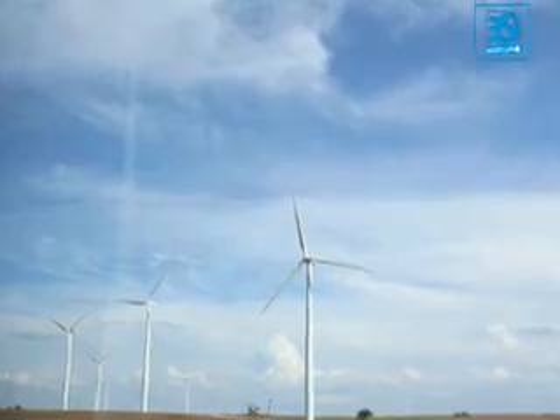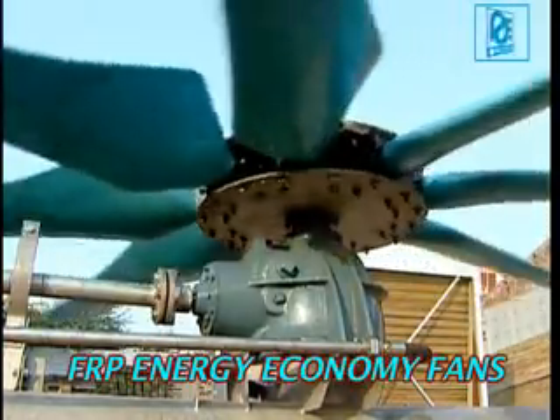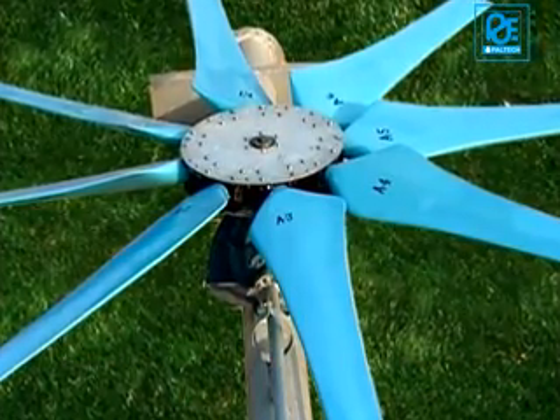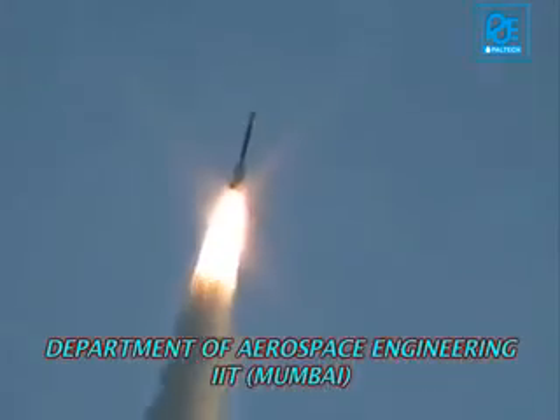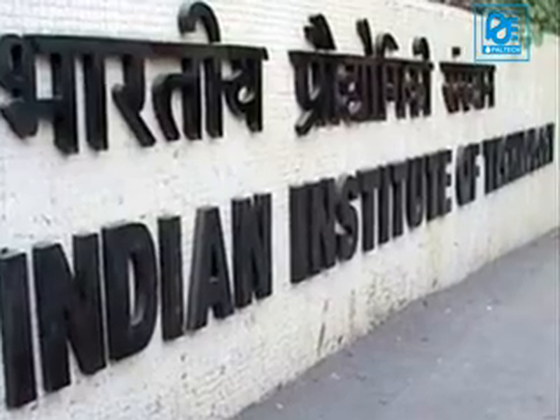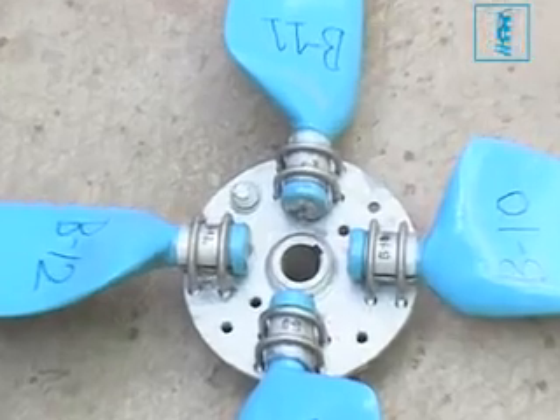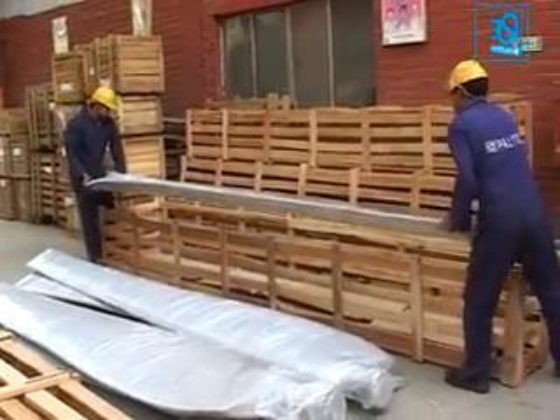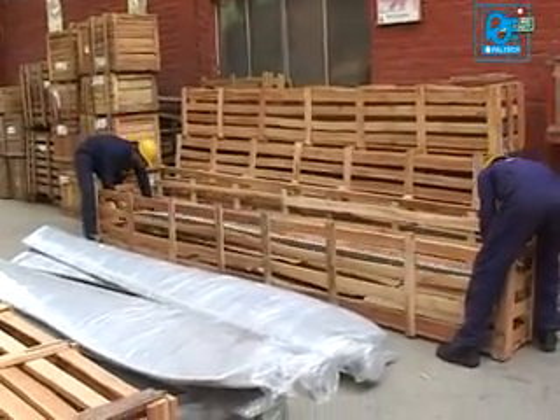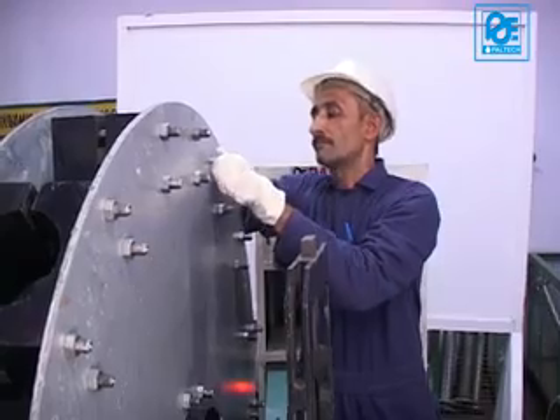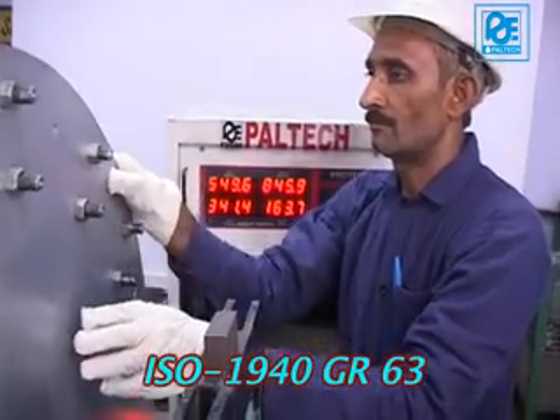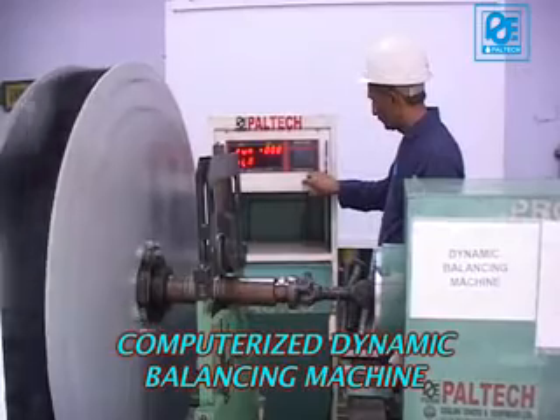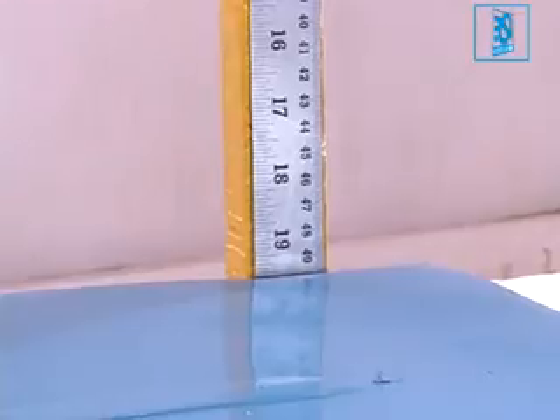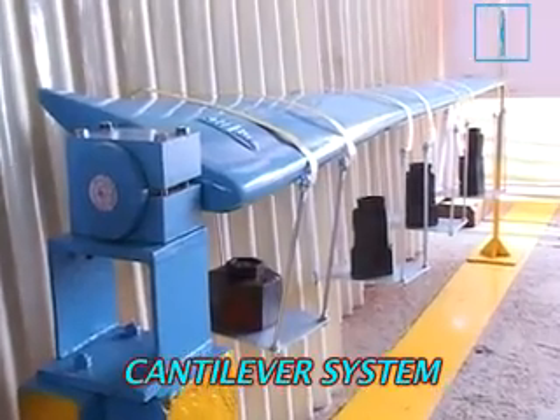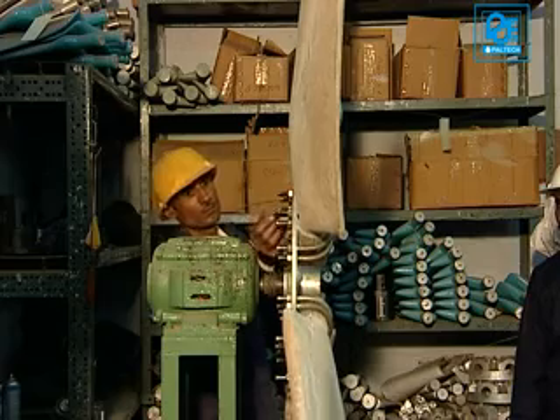With a mission to conserve energy by reducing the power consumption, Paltech developed FRP energy economy fans with the design assistance from Department of Aerospace Engineering, IIT Mumbai, one of the premier technology institutes. No wonder Paltech is a synonym for tough, strong and durable cooling tower fans. The hub assembly is balanced as per ISO 1940 G6.3 on computerized dynamic balancing machine. The blades are checked for their load testing by cantilever system and then are checked for perfect match moment.